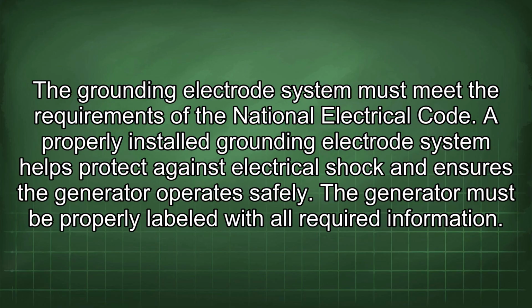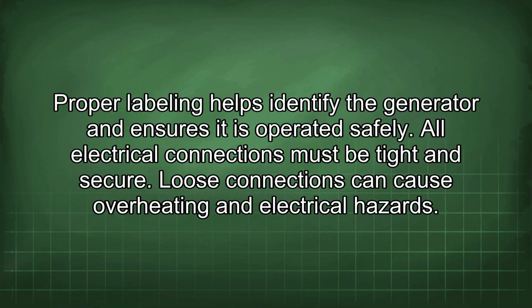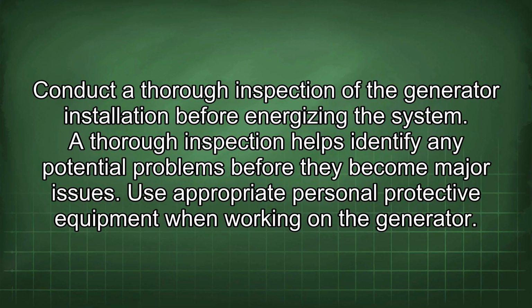The generator must be properly labeled with all required information. Proper labeling helps identify the generator and ensures it is operated safely. All electrical connections must be tight and secure. Loose connections can cause overheating and electrical hazards. Conduct a thorough inspection of the generator installation before energizing the system. A thorough inspection helps identify any potential problems before they become major issues.